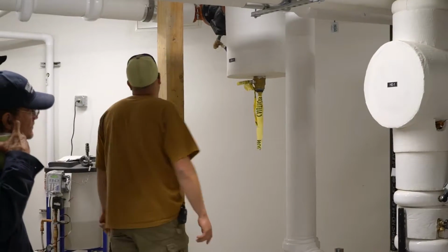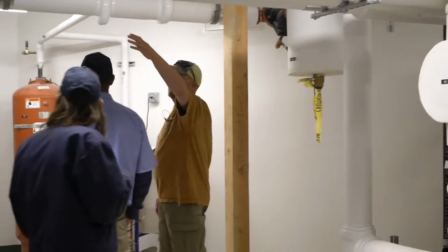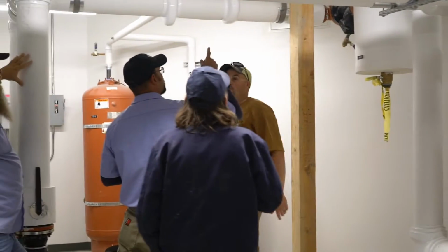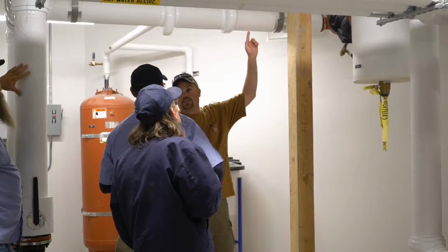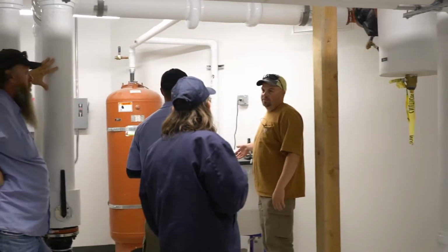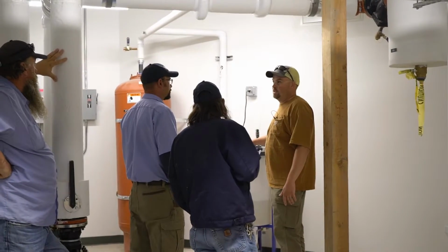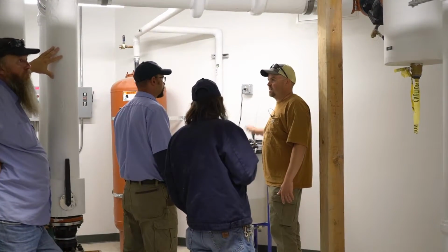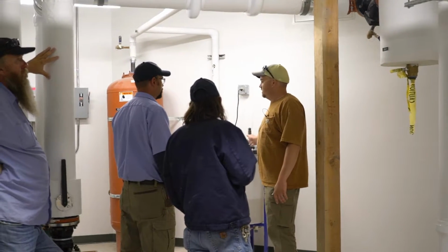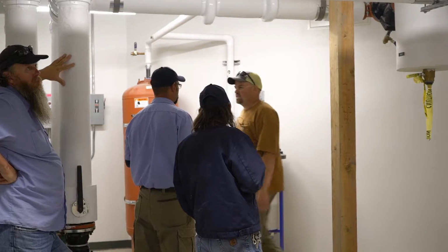So basically, it'll come up through your air separator, getting sucked through your pumps, and then out and down in your crawl space with branch lines. There is an air vent on top, yes. Glycol feeder, I believe Snowcrest, the chemical guy, programmed that to kick on at 13 psi, like when it gets down to 13 pounds, then kick off at 18. Okay. And our operating pressure here is? It's about 18, 16, 17.